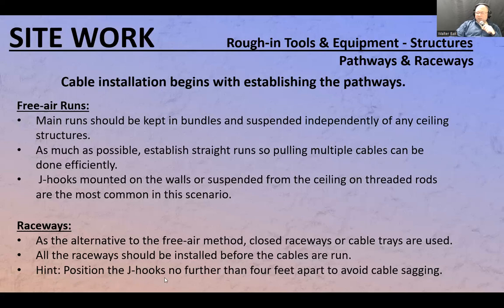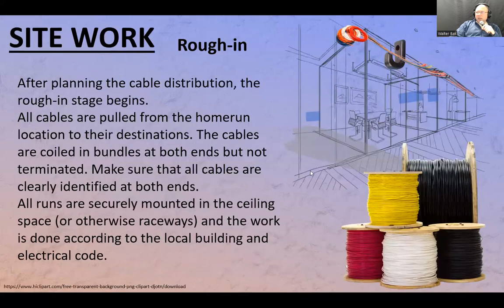Hint: position the J hooks no further than 4 feet apart to avoid cable sagging. Quite often this line is included in the contract, that the J hooks are supposed to be no further than 4 feet apart. If you put those J hooks too far apart, those cables are going to sag, and you'll get that wavy look.